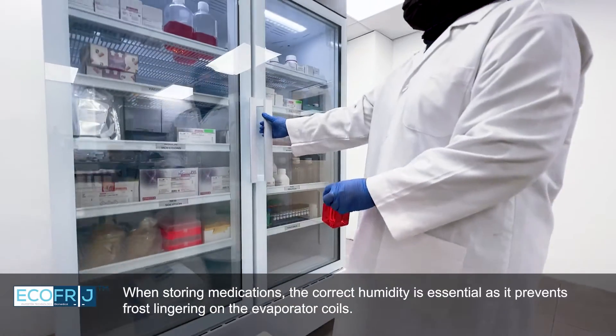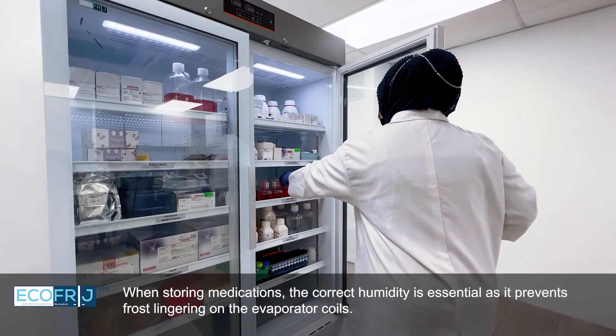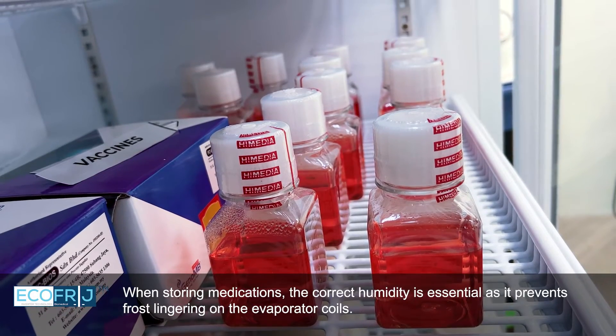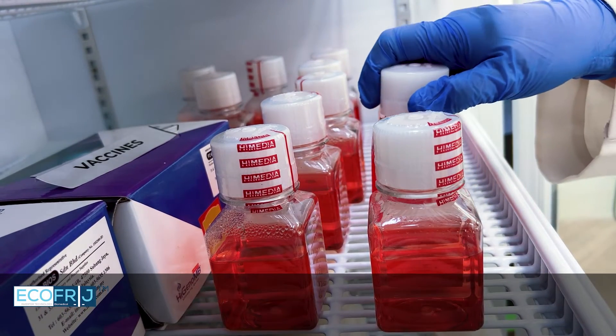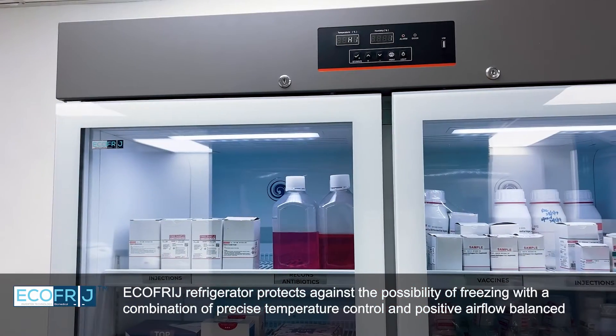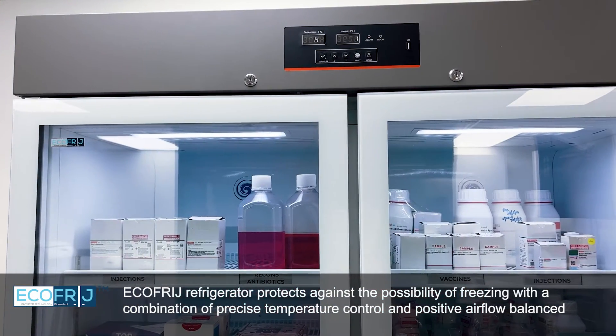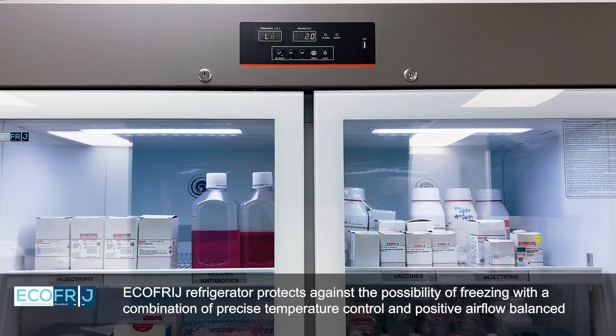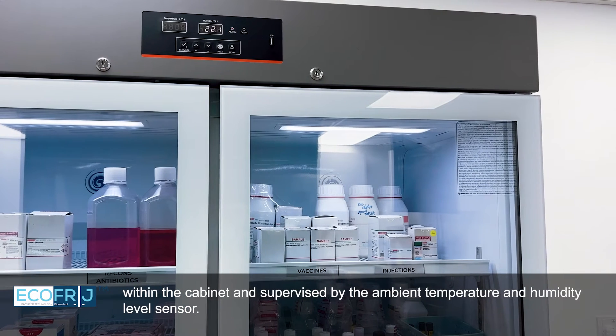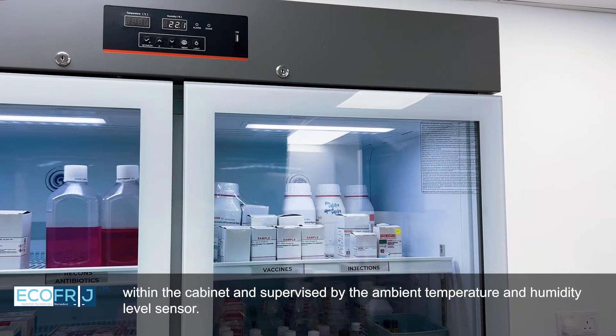When storing medications, the correct humidity is essential as it prevents frost from lingering on the evaporator coils. EcoFrij refrigerator protects against the possibility of freezing with a combination of precise temperature control and positive airflow balanced within the cabinet, supervised by an ambient temperature and humidity level sensor.